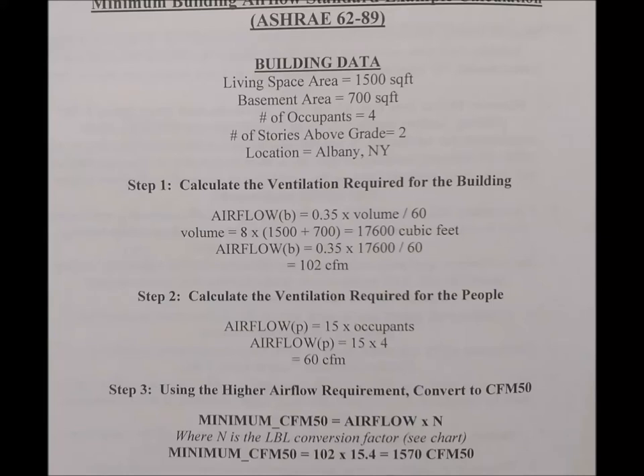Whenever changes to the building require a blower door test as part of the work scope, a building airflow standard must be calculated for the home according to the air exchange requirements provided by ASHRAE Standard 62-89. Actual occupancy of the building must be used when calculating the building airflow standard. An example of the calculation is shown below.